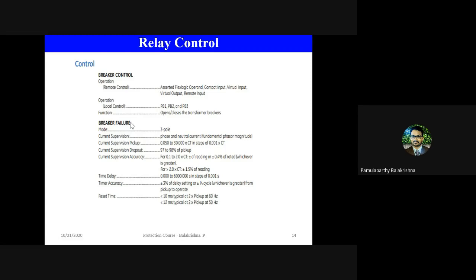If by any chance the breaker component fails to operate, the fault will not be addressed and the asset will undergo stress. So in order to avoid such a condition, if a particular breaker doesn't operate for a certain duration of time, and the current level is still persisting above a certain level that can be configured, then the relay will automatically send a signal to the upstream breaker which is connected, which can trip the circuit where the fault occurred. So the relay first trips the local breaker.